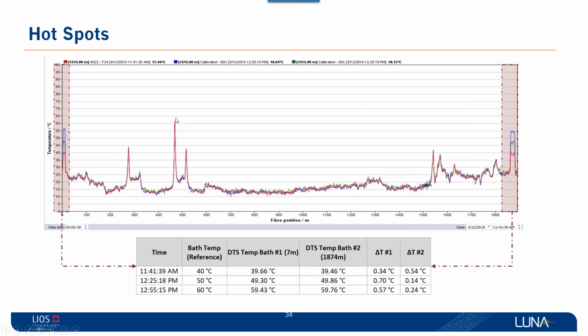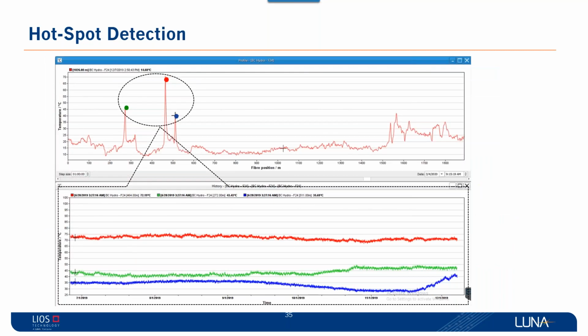Automatically, you can see between 60 and 65 degrees Celsius is the fiber temperature. This is already a red flag because that simply means your conductor temperatures are probably higher. As you can see, of the three hotspots, the red one is the hottest, operating around 70. This temperature is not changing that much, but you can see that the blue one is changing a little bit based on season. So the circuit of interest is the circuit surrounding or crossing the steam, where the steam line is crossing, and that's what we're going to analyze.